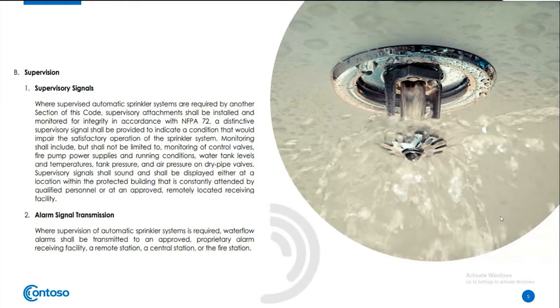So doon naman tayo sa alarm signal transmission. The intent of this is to allow the newly developed technologies to be used that meet requirements in section 26.6, that is the communication method of supervising station alarm system, and section 10.6.7, the secondary power supplies, because new technology has been proven to provide a reliable alternative to phone lines.